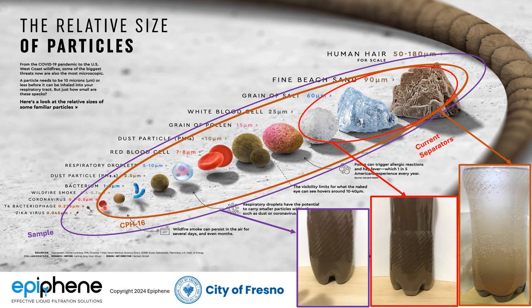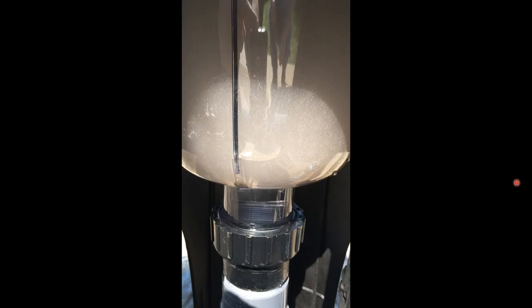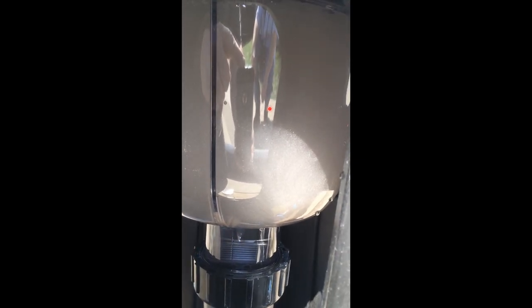When we're looking at the cooling tower industry and many other industries, if we can get down to five microns or better, we can typically provide drinking water clarity or close to it. Let's look at the separation of solids at the beginning of the flush process. Note the inlet water is pretty clear — you can see a little bit of solids — but after it goes through the separation, the solids fall out and accumulate.